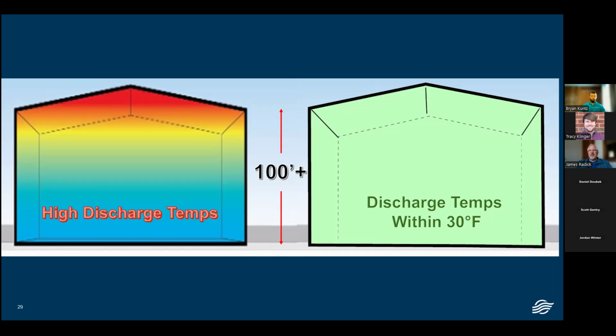In fact, I can say without a doubt, I know of no building that has a direct fired piece of equipment, that does this kind of concept, that didn't have an improvement in air quality after the system was installed with direct fired. You can't say that about other types of heating systems, unfortunately. Indirect fired equipment, etc. It's not a question of if, it's a question of when, etc. So properly maintained burners here, they are really fantastic performers.